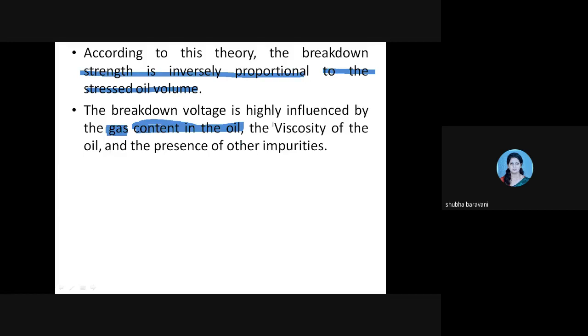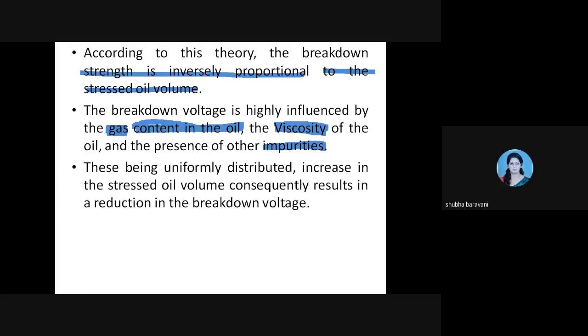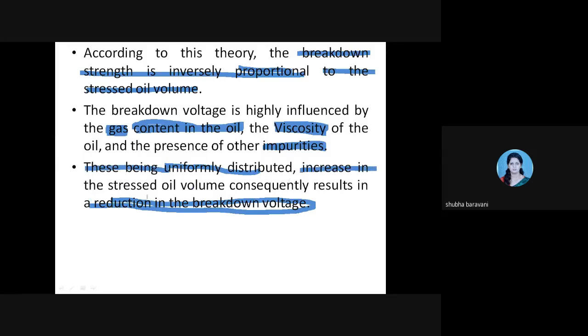The viscosity of the oil also forms a reason for breakdown, as well as the presence of other impurities — solids, fibers, or gaseous impurities. Being uniformly distributed, an increase in the stressed oil volume consequently results in a reduction in the breakdown voltage. Breakdown strength is inversely proportional to the stressed oil volume. This is the stressed oil volume theory.